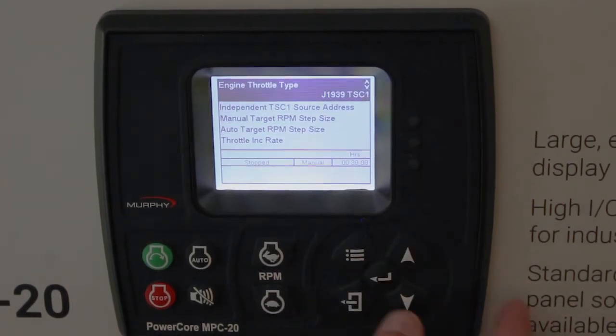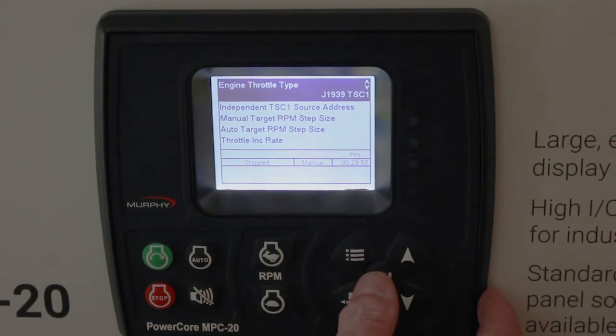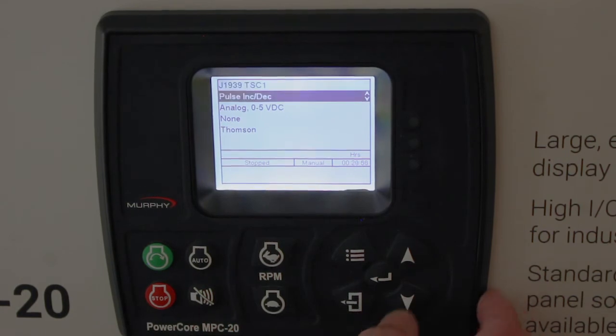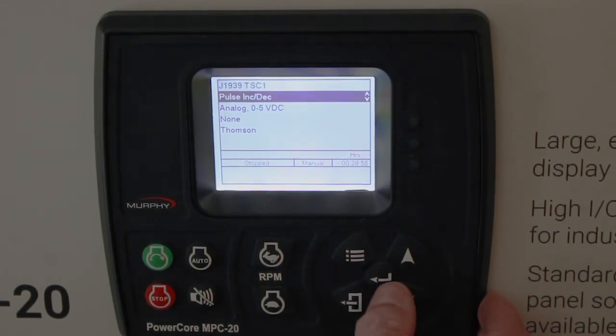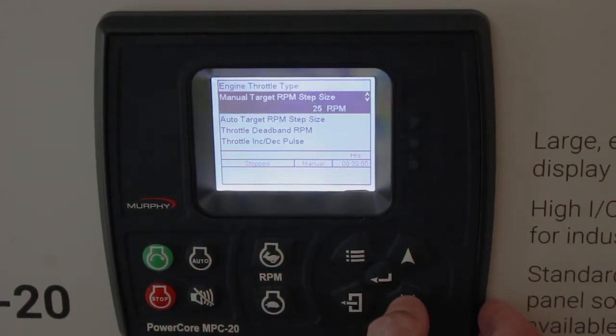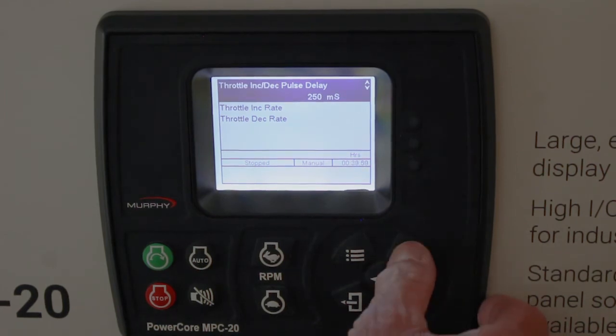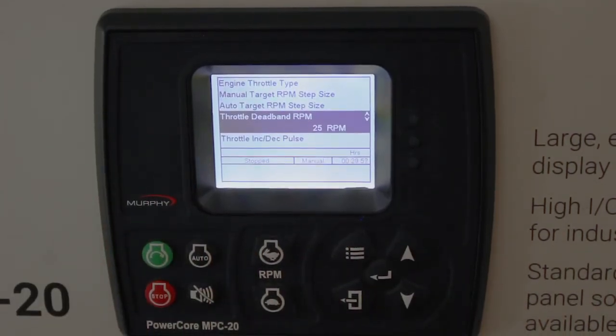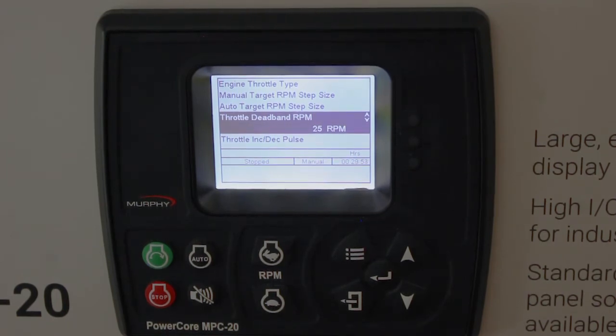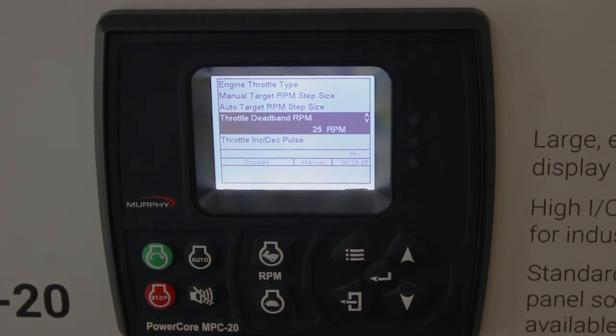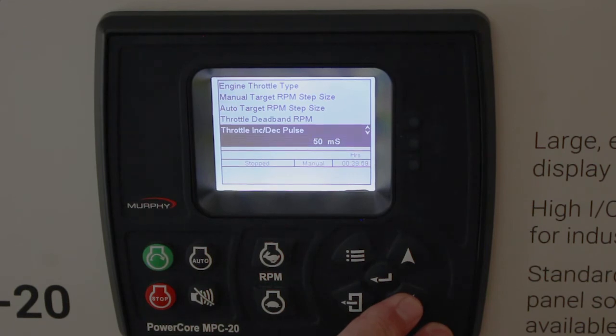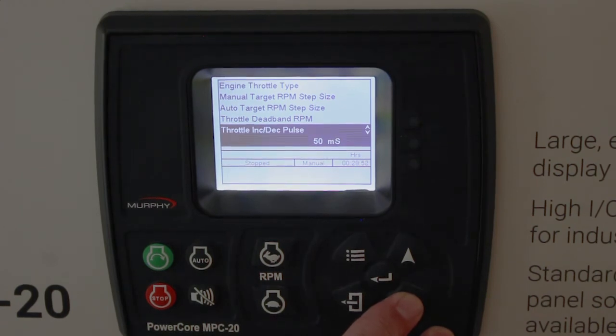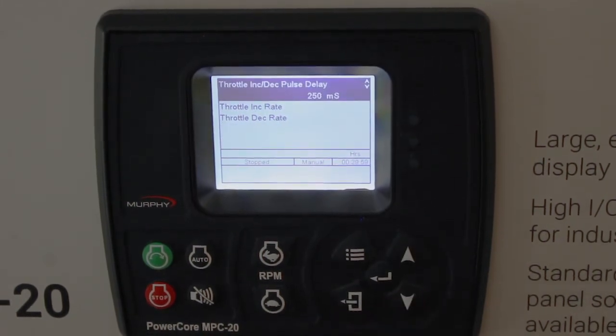If I choose pulse dec — because I have a mechanical engine — I'm going to get something called a dead band. You don't get that with TSC throttling. That means if we throttle an engine and we're within 25 RPMs of our target RPM, we're happy and we quit throttling. You can raise or lower that as required. We also have pulsing outputs — inc and dec pulse outputs — that you don't have when you choose J1939 throttling. And there's a delay: you get a certain amount of pulse out to our throttle actuator and then a delay between pulses. So you get a few more set points depending on what you choose for throttling type.